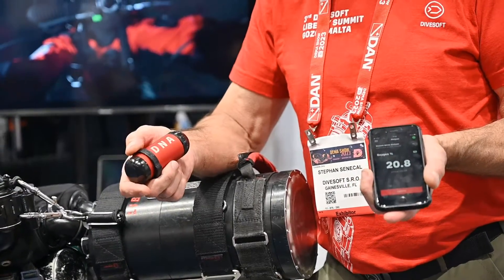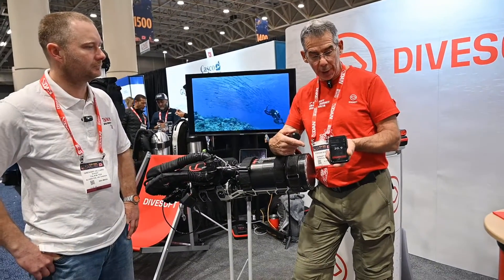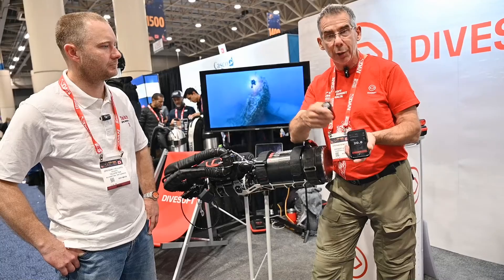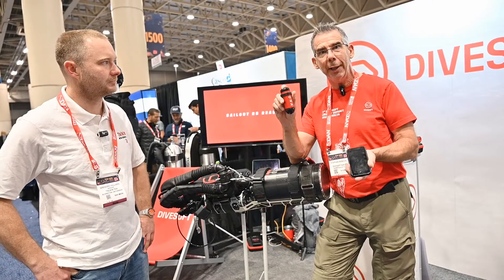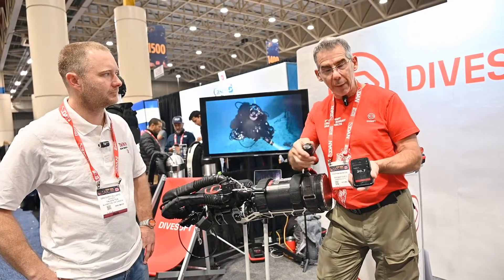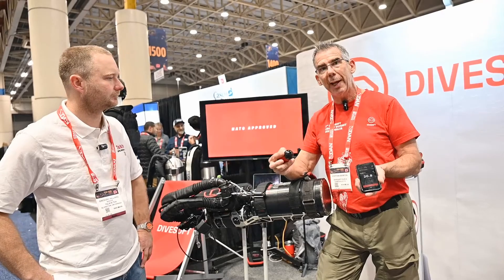You can calibrate it with air, you can calibrate it with oxygen. It will give you the status of the small oxygen cell, the battery that costs almost nothing, and you can see the charge of it. Then you can follow your reading.